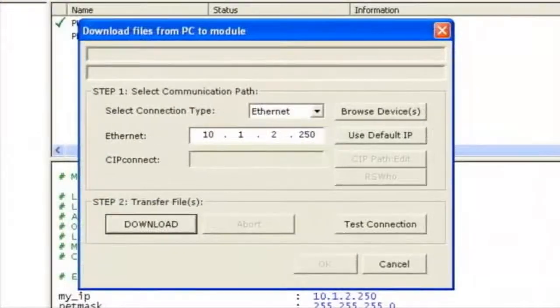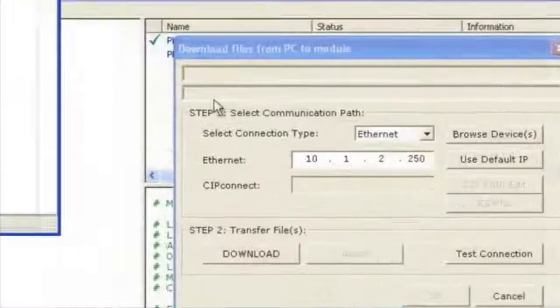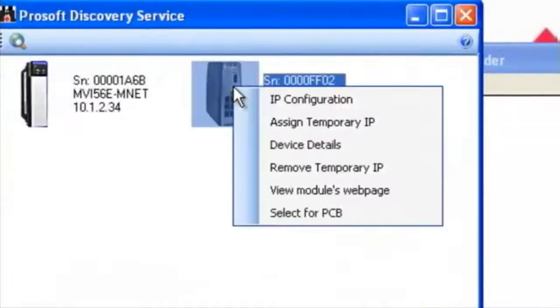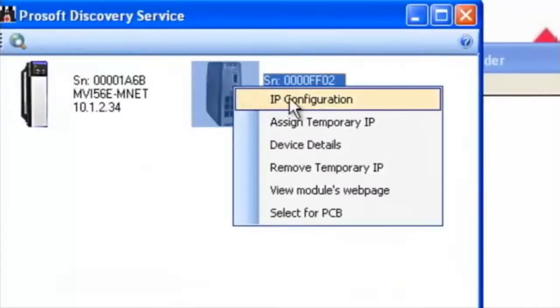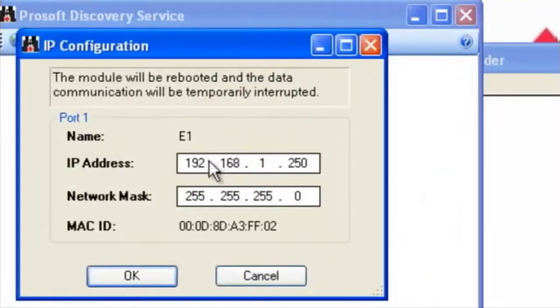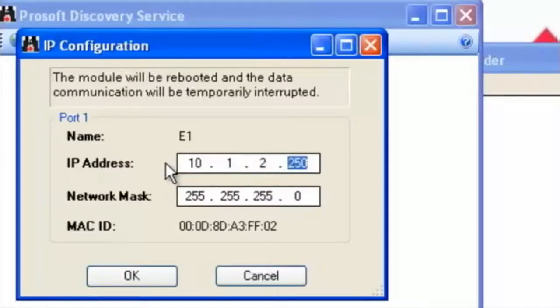Once this is done we're going to select browse devices and this will launch our ProSoft Discovery service. Here we can right click on the module and configure the IP address to the actual module so we can download via Ethernet. I'll change it to 10.1.2.250 as well.